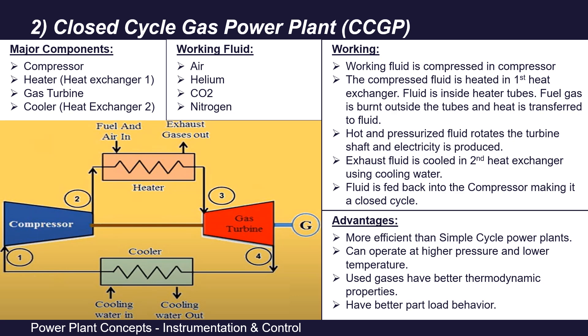The major components of a closed cycle gas power plant are a compressor, then a heater, then a gas turbine, and finally a cooler. The working fluid can be air, helium, carbon dioxide, or nitrogen. First, we compress this working fluid in the compressor. Then this compressed working fluid is passed through the heater tubes in a heat exchanger — the working fluid is inside the tubes, and outside the tubes a fuel-air mixture is burnt, producing heat that heats the compressed working fluid.